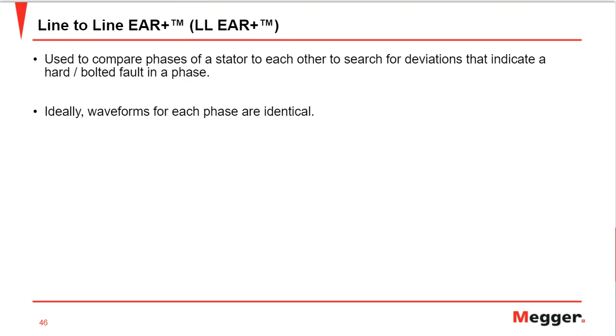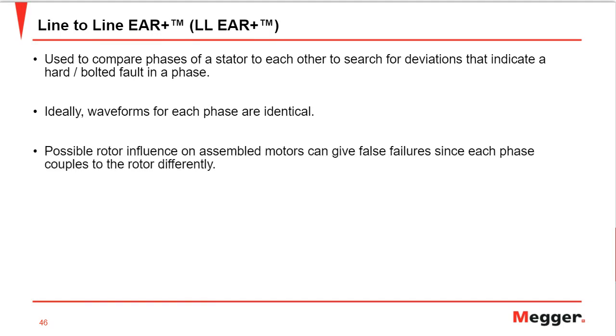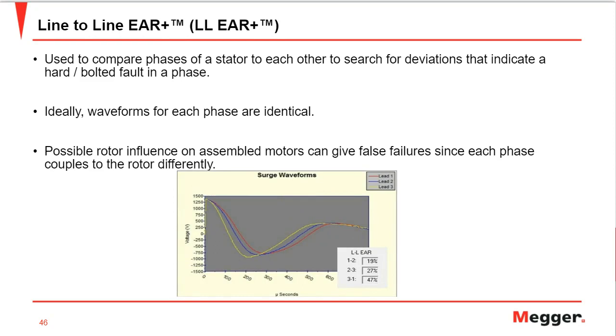The thought here is that the surge waveforms for all three phases of a motor should be nearly identical. So if the waveforms are not, there should be a hard or bolted short in one of those phases. That's what line-to-line EAR would help us determine.